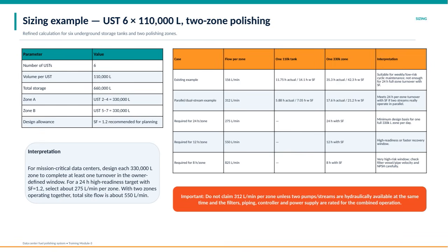Looking at flow requirements, the existing example shows a flow of 156 liters per minute per zone, which translates to about 14.1 hours with the safety factor for a 110,000 liter tank, and about 42.3 hours for a full 330,000 liter zone. This is suitable for weekly or low-risk maintenance cycles, but insufficient for a full 24-hour turnover. If 2 parallel or dual-stream systems operate simultaneously at 312 liters per minute, then a 24-hour turnover per zone is achievable with the safety factor.